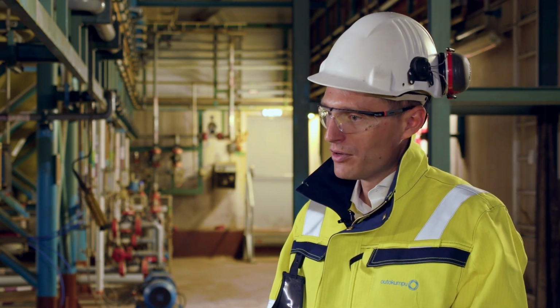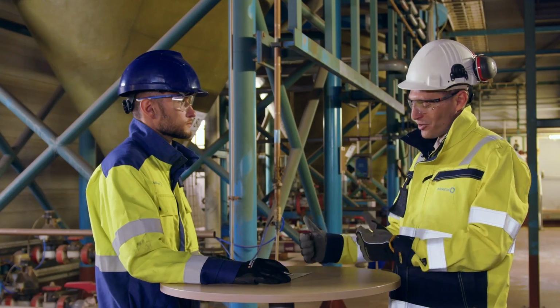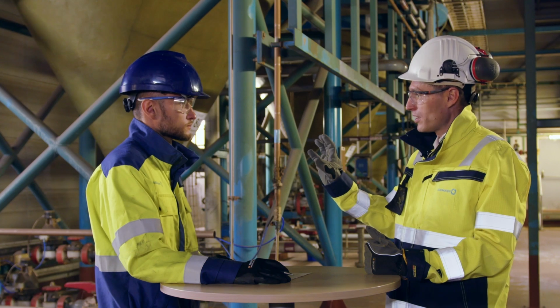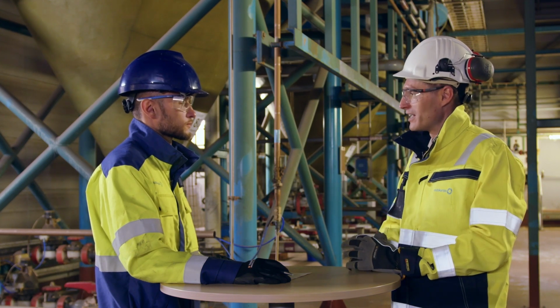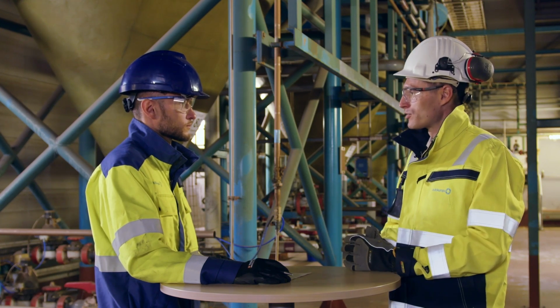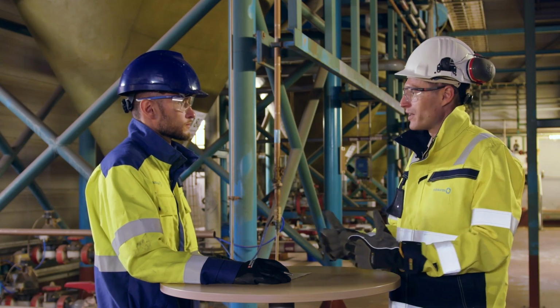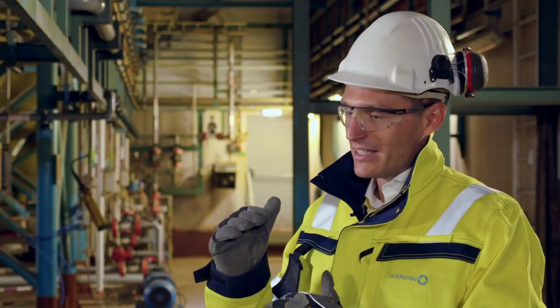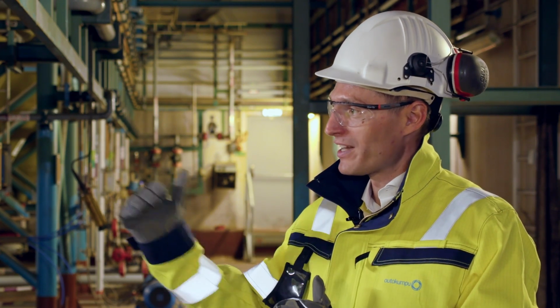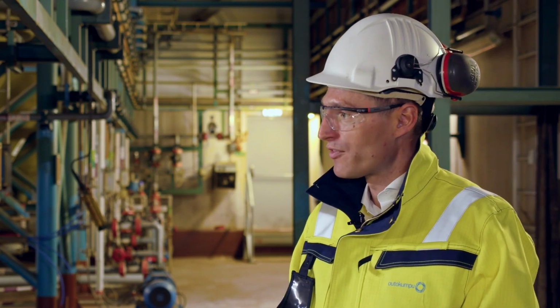So what we do is we send, for example, the robot here in Avesta in the asset regeneration plant to different areas. We take inspection points on that mission on the different levels in that specific facility. We send that information into the control room, interpret it sufficiently, and then take measures based on deviation. So we are actually not interested in the values between the upper and lower control limit. We are looking more into trends and deviations.